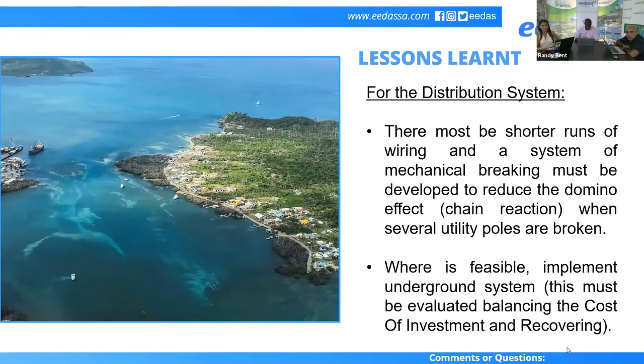As we said before, the shutdown of the grid reduced the electrical damage to the transformers. These equipments are heavy to get in this kind of emergency; they have to be made or deployed from the mainland, which takes about 15 days. So the idea is to reinforce the structure, use heavy resistant poles to install these distribution transformers, and also deploy the shutdown in case of another event like this.